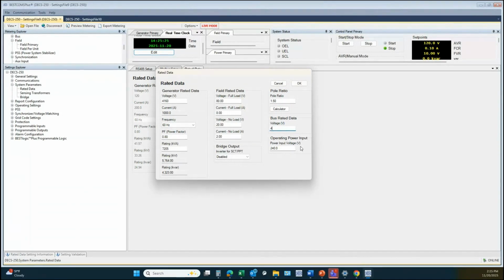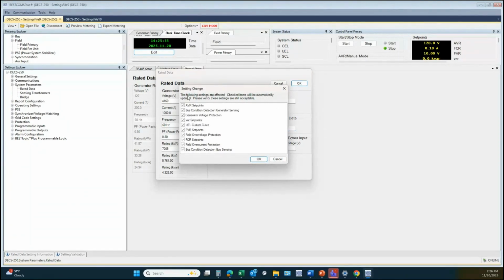Rated bus voltage, not necessary unless you plan to perform synchronizing or the sync check functions, but it's generally similar to the rated generator voltage. Operating power input. This is the bridge power input or PMG. Once you have set these, then you can select OK. It will give you some notifications that some of the other settings are going to change based upon that. Again, as I mentioned, these settings do affect the set point ranges for the different modes of operation.